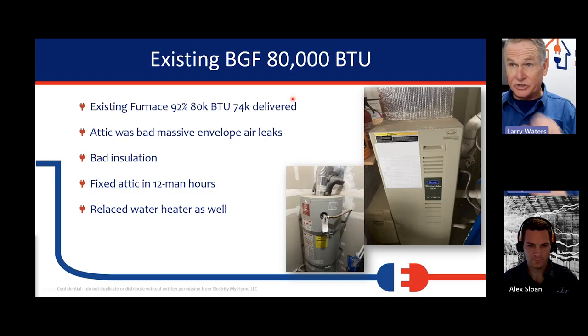We took out an existing big gas furnace, an 80,000 BTU system. It was a 92% unit, 74K delivered. The attic was really, really bad. It had huge envelope and air leaks. In fact, the pictures I showed you before of looking down on the china cabinet were from this house. It was massive envelope air leaks.